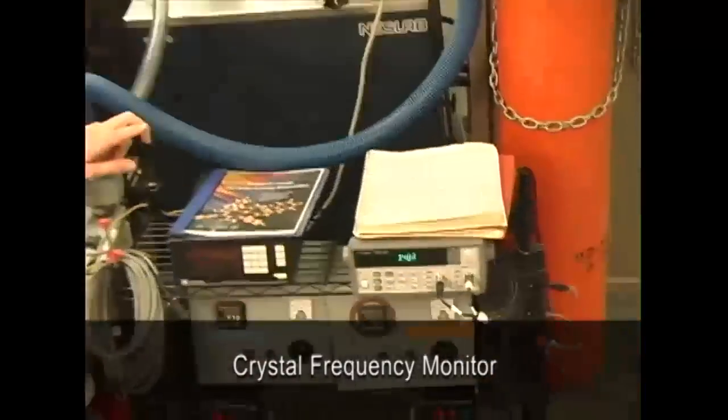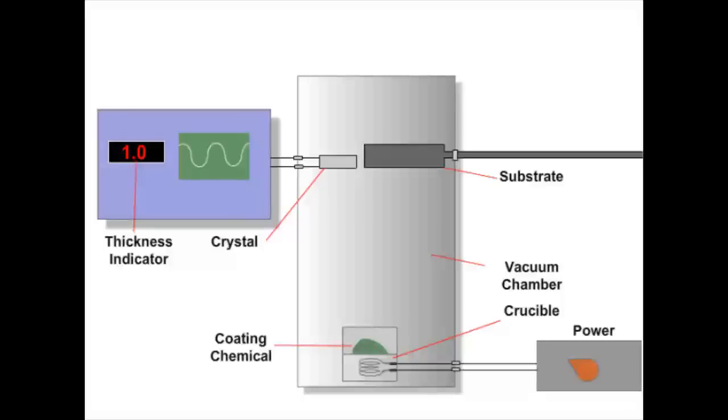We monitor the deposition with the frequency counter. There is a quartz crystal inside the chamber which is coated with organics along with the device. As the thickness of deposit increases, the frequency of the crystal changes at a known amount depending on the molecules. This allows us to control the thickness of each organic layer precisely.